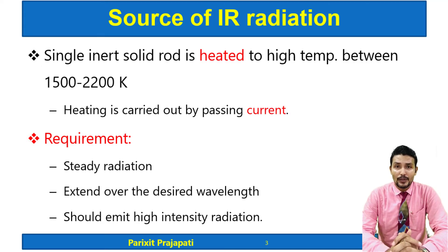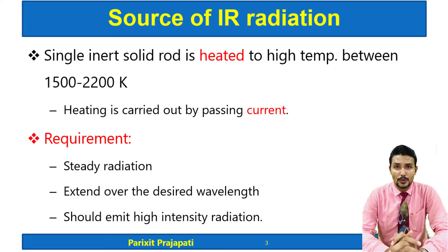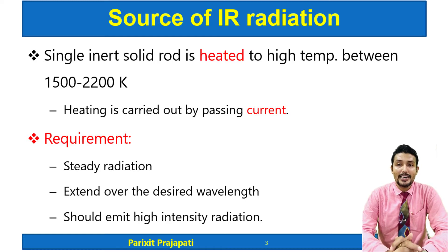In IR spectroscopy, we work with mid-IR more specifically for qualitative purposes, and we also work with near IR. So depending on the working wavelengths, the source should provide the desired wavelength. It should also emit high intensity radiation so that it can be detected by the detector.